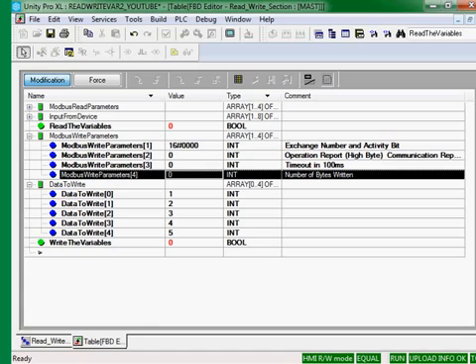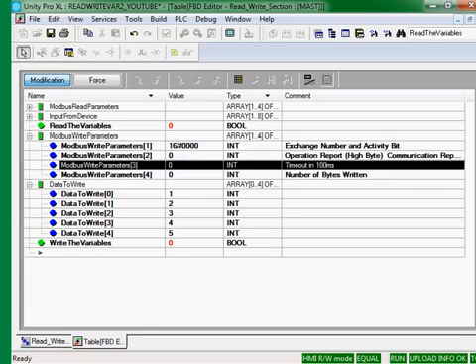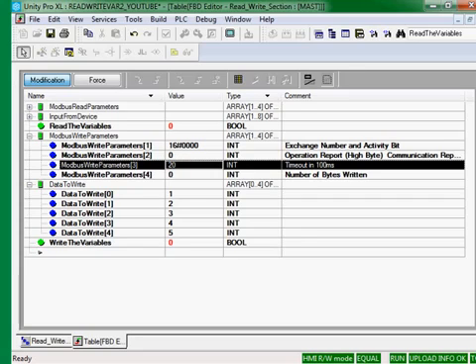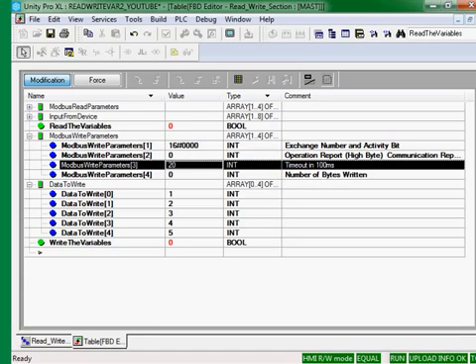These are the Modbus write parameters. Again, we know we need a timeout because that is very important because if the cable were unplugged, the timeout of zero is infinite. And we don't have that long to wait. So the data we're going to write are the values of 1, 2, 3, 4, and 5. We'll write those values into the 100th register of the Modbus device.